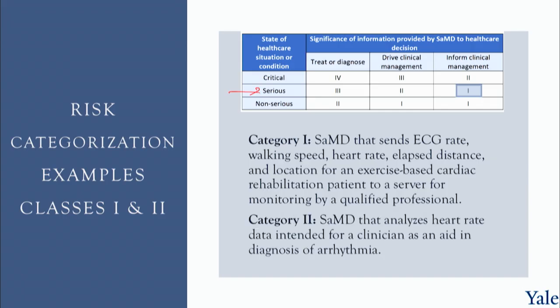Moving up to Class 2: this is software that analyzes heart rate data intended for a clinician as an aid in the diagnosis of arrhythmia. The condition is still serious — still a cardiac condition — but the output is used as an aid to diagnosis, not the sole factor. So we're driving clinical management.